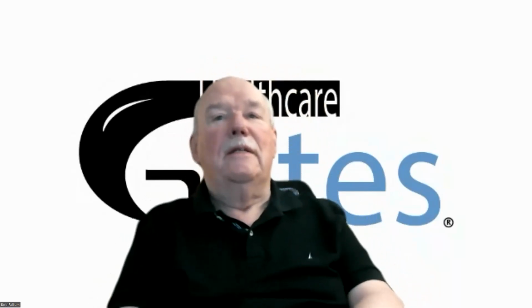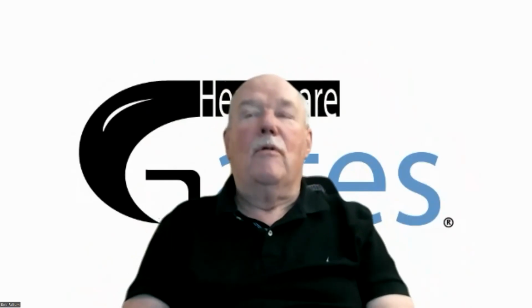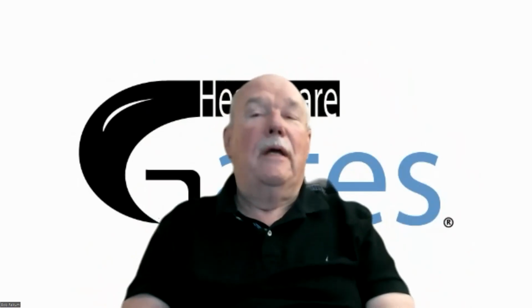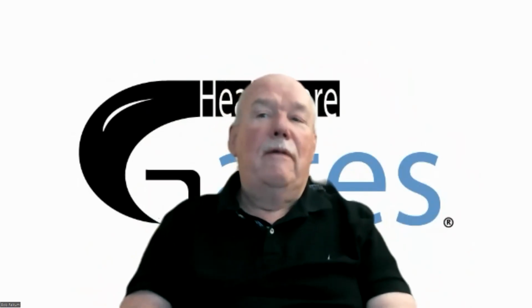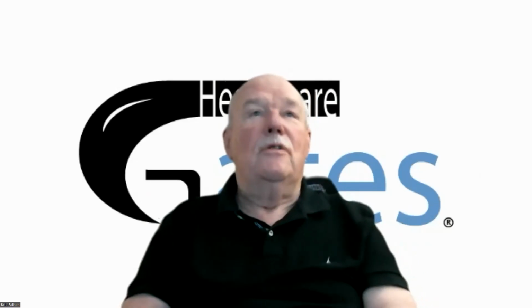Now looking straight up, the next thing, which I think is kind of buried, is that you need returns placed low, as we discussed. The return should be placed so you get unidirectional flow, even though it's jagged, sweeping away from the hoods and coming back. That's the reason for the 6 inches - you leave 6 inches off the floor for cleaning.